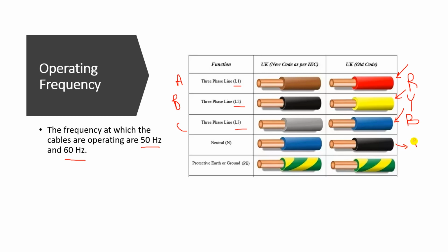The neutral color is black, and the earth can be green or green and yellow, like this. This is the earthing, or the protective earth, or the grounding wire. These are the colors used by the UK in the old code. In the new code, according to the IEC, they use brown for phase number one, black for phase number two, and gray for phase number three. For the neutral they use blue, and for the protective earth they use these colors.